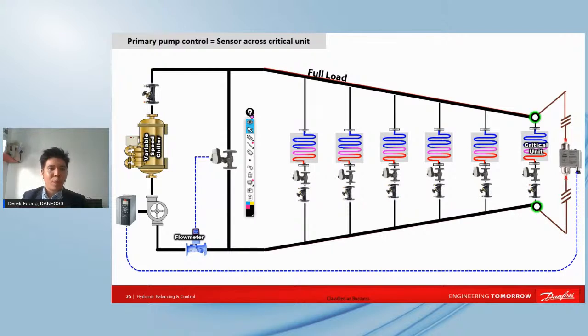And let's move to one of the methods we encourage most end users or designers to actually use, what we call proportional pressure control. And how do we achieve proportional pressure control? This is one of the most efficient methods while keeping the right capacity in the system. And most of the time, this critical unit is very important, and it's not necessarily the furthest. All right, so I repeat it again, it's not necessarily the furthest. The critical unit is the highest pressure drop unit in the system. All right, bear in mind.